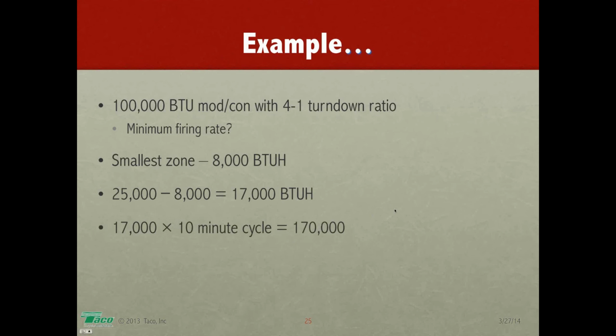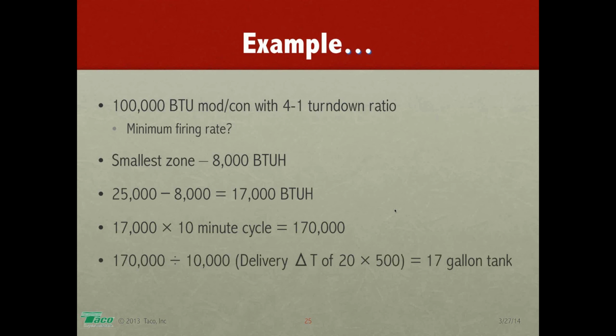Next, we multiply 17,000 BTUs by our minimum desired 10-minute burn cycle. 17,000 times 10 gives us 170,000. Now, to find the size of the tank, we divide 170,000, the cycle factor, by the delivery side delta T of 20 times 500, which is 10,000. 170,000 divided by 10,000 gives us a 17-gallon tank. So what we would need to do is find something as close as we can to a 17-gallon tank.